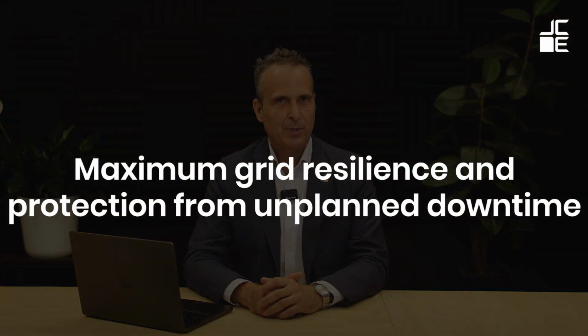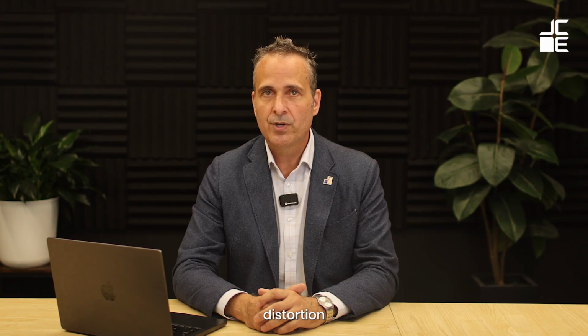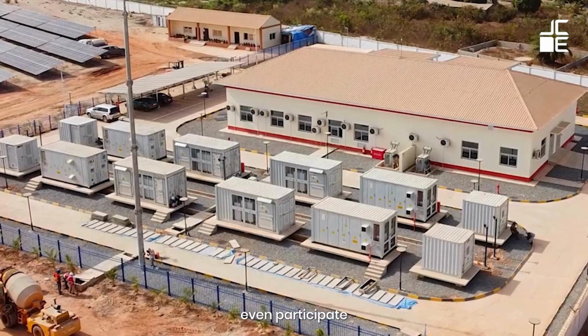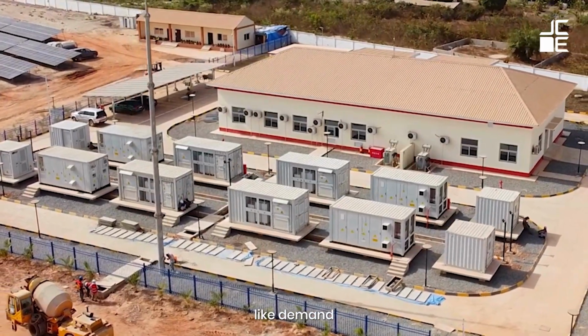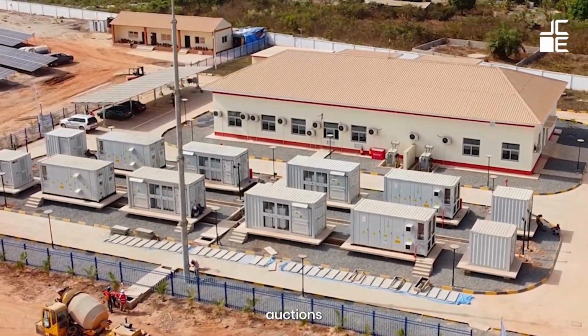How does this benefit you? Maximum grid resilience and protection from unplanned downtime. Double conversion efficiency of around 96%, or up to 99% when running in static bypass. No harmonic distortion on your main transformer, and with extended battery duration, say 2 hours, you can even participate in grid programs like demand response or capacity auctions.